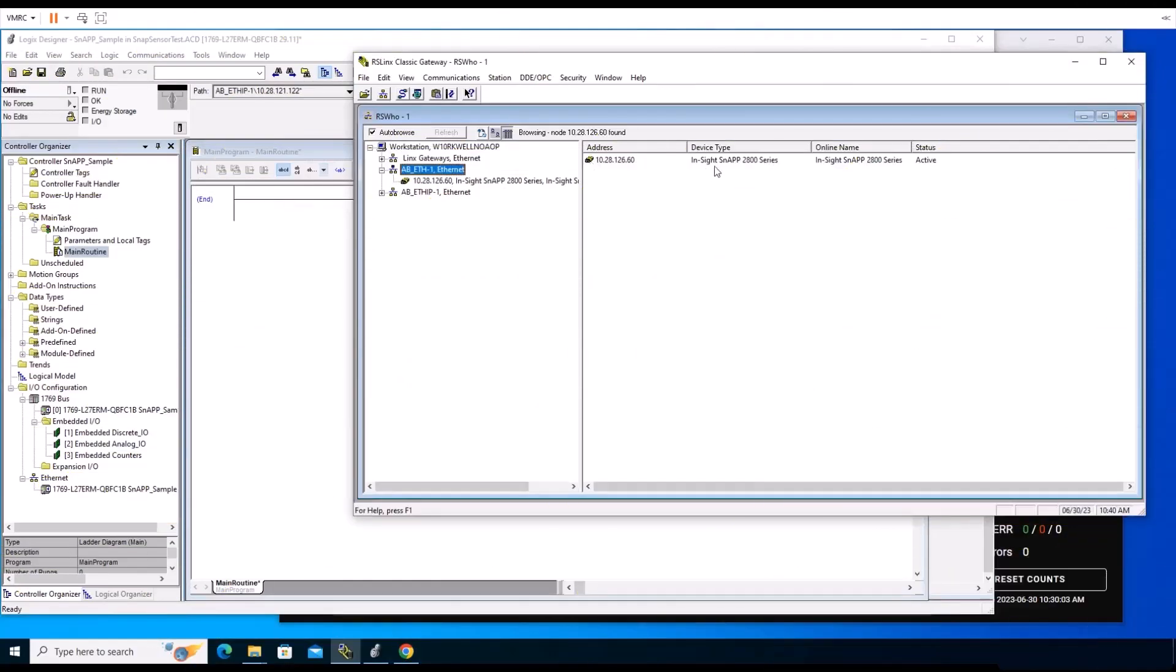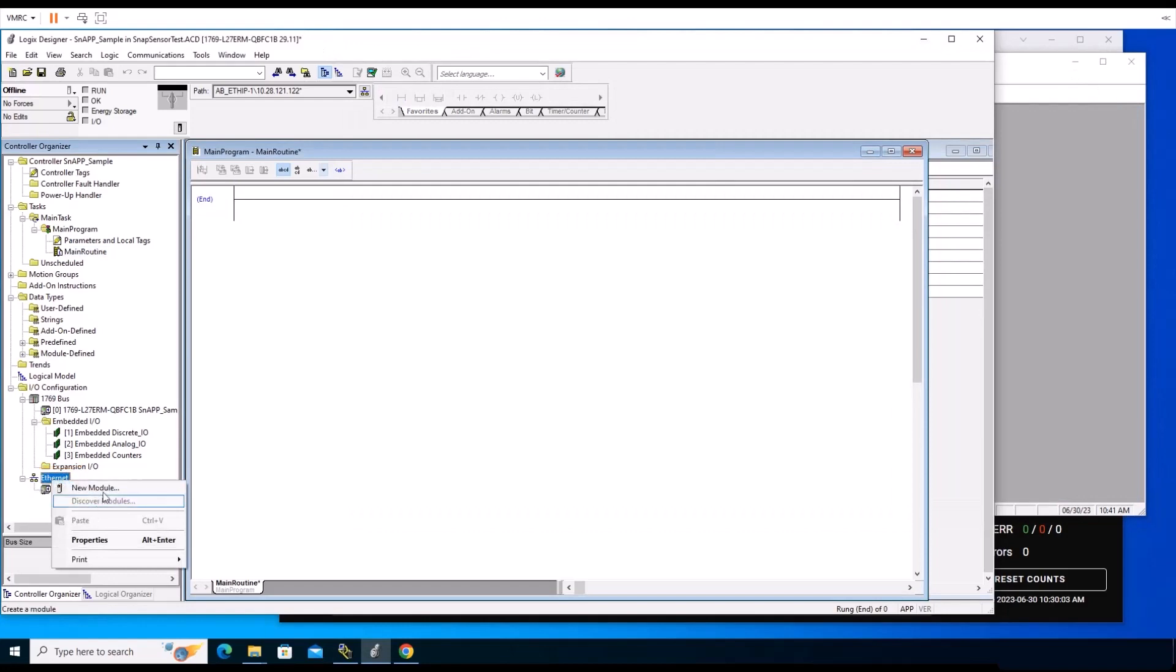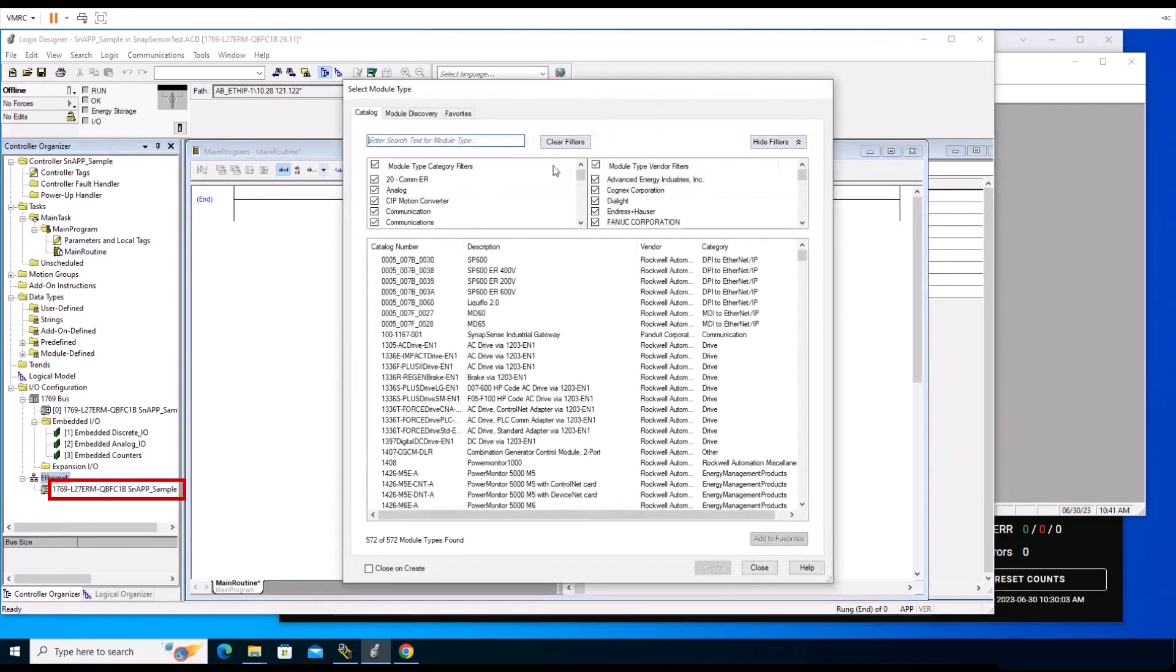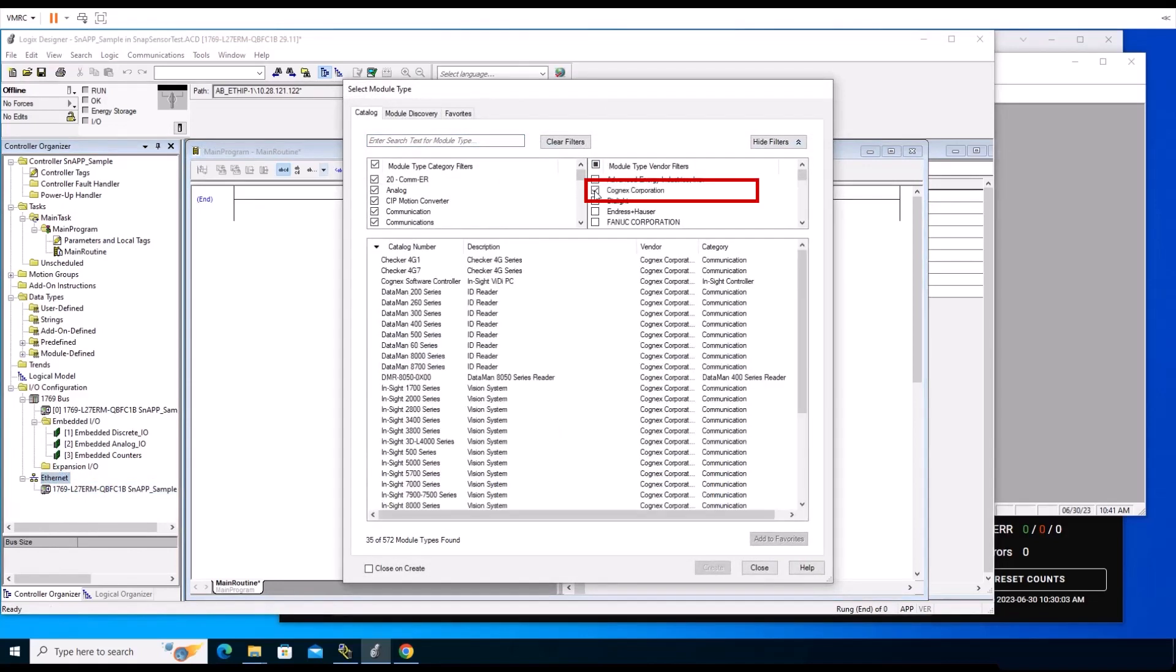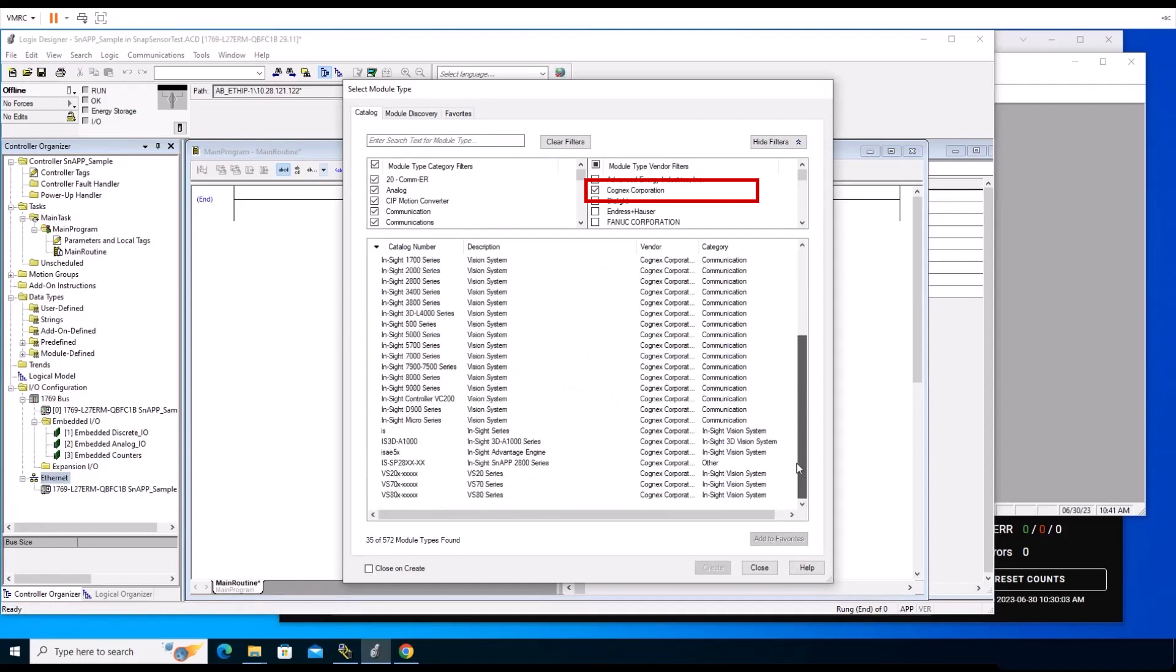Once the Rockwell EDS installation is complete, navigate to Logix Designer within the Controller Organizer list and right-click Ethernet. Select New Module from the Option list to create a new module. The Select Module window displays. Filter through the Cognex devices to select the appropriate module type. Check Cognex Corporation under Module Type Vendor Filters and locate your InSight SnAP sensor in the Module Type list.